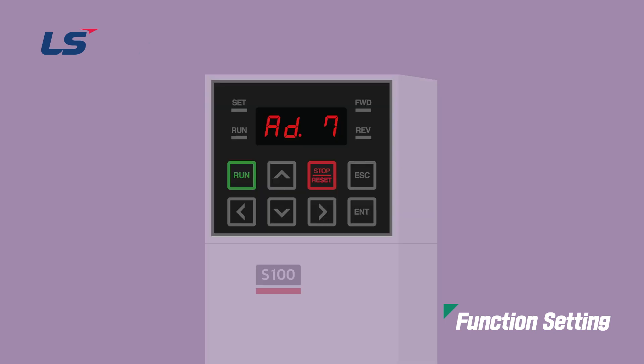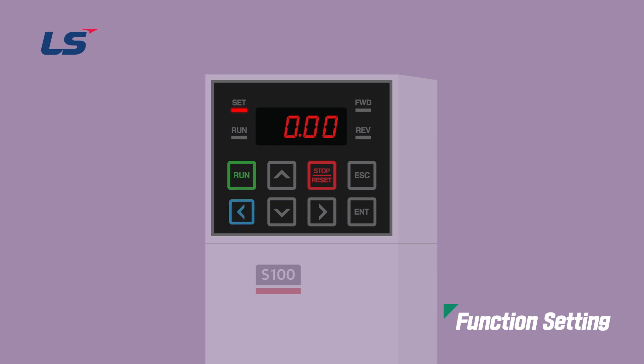Select DC start as number 1 in AD7 start mode. When DC start is set, DC start time in AD12 and DC injection level in AD13 are activated. At AD12 DC start time, press enter and use the arrow keys to set the time. The time setting can be set from 0 to 60 seconds depending on the condition of the equipment. At AD13 DC injection level, press the enter key to set the DC injection level. Use the arrow keys to set the level and press enter to complete the setting. The DC injection level can be set from 0 to 200% depending on the machine condition.